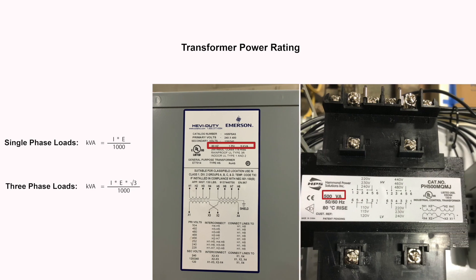Transformers are rated in volt amperes, VA, or kilovolt amperes, KVA. Volt amperes is the total power supplied to the circuit from the source and includes real, watts, and reactive, VAR, power.